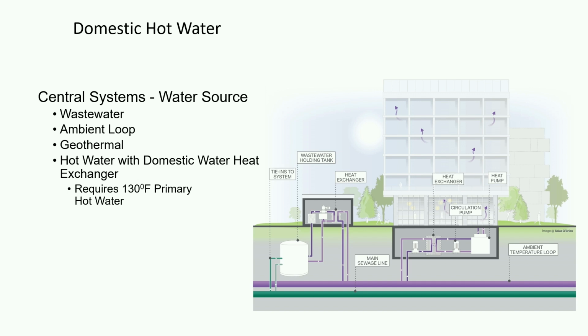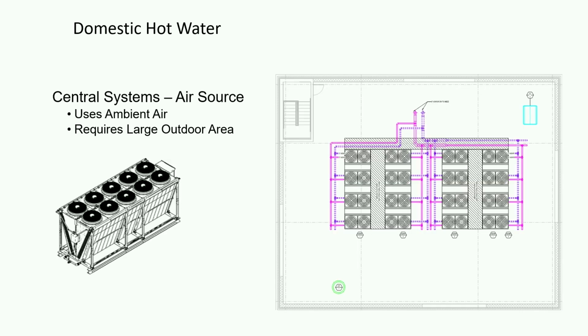So that's all a really great technology now, and there's a lot of heat pump technology in that space that's become more available for reaching the 130 to 140 degree temperatures, working off of geothermal sources, with different refrigerants. So that's a really great technology to also incorporate into the design and really help try to balance that profile and bore field energy for the long term. And, we mentioned this, there's obviously some central air to water systems that can be incorporated into domestic use, but that would have to take up some roof space.